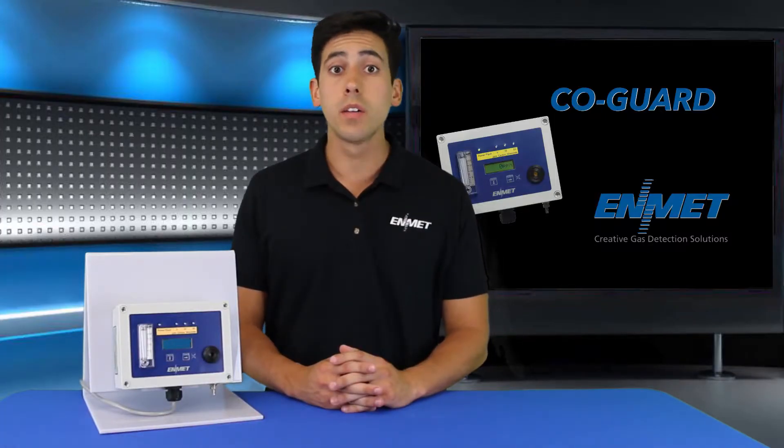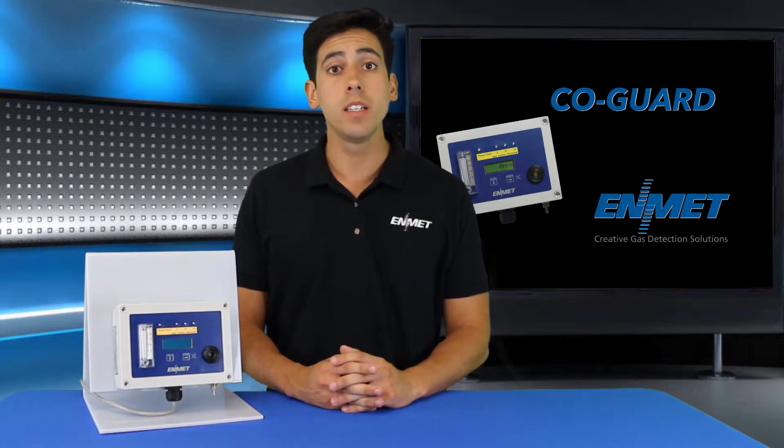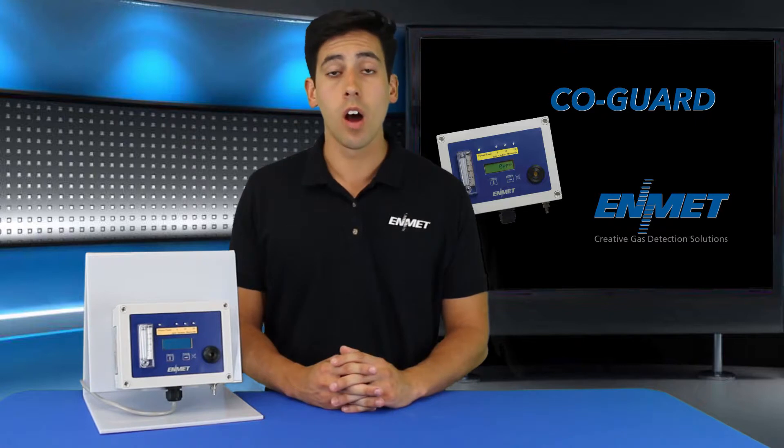The CO-GUARD includes a backlit digital display and audible and visual alarms with three alarm levels. The power LED also doubles as a fault indicator should a fault occur. The audible alarm features a four-minute audio defeat option for alerts below alarm level three.